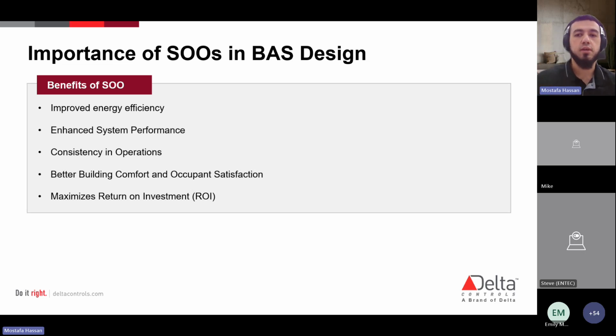Also, you have consistency of system operation, right? In various scenarios, you have occupied, unoccupied, heating and cooling. That's all going to be outlined in your sequence of operation. And that consistency will help the operators manage the systems more effectively. Building engineer, maybe sitting somewhere in the basement with a workstation looking at different faults and things that are happening in the system. Having everything programmed or scheduled properly will allow them to focus more on one issue, right, or prioritize issues as they roll in.